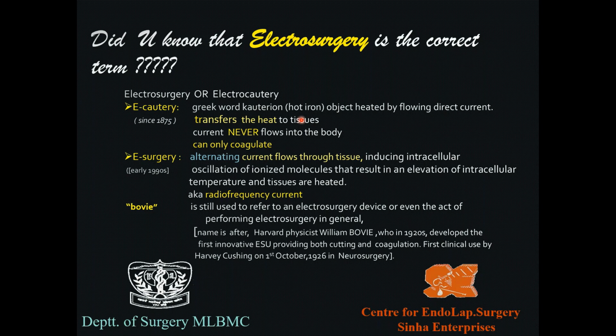But what is electrosurgery? Electrosurgery is the correct term for what we normally use for coagulation or for cutting purposes, when we are using a machine which we commonly term as electrocautery, which is wrong. So it should be electrosurgical unit. Started in early 1900s. Alternating current flows through the tissue. Sorry, this should not be 1990s, early 1900. Current flows through the tissue, inducing intracellular oscillation of ionized molecules inside the cell, which results in elevation of intracellular temperature and tissues are heated. It's also known as a radio frequency current.